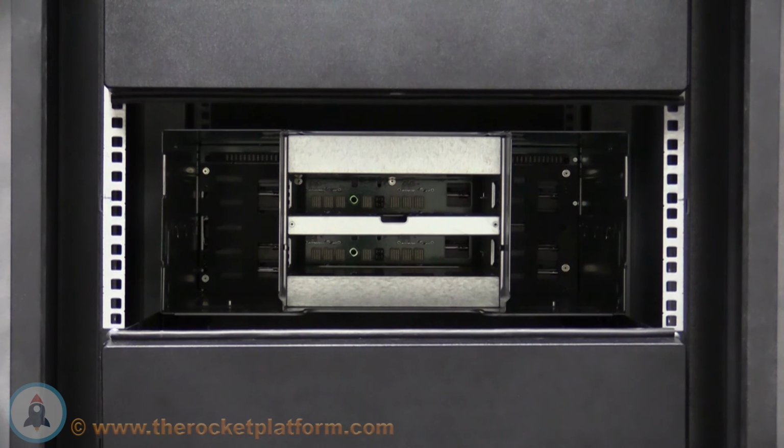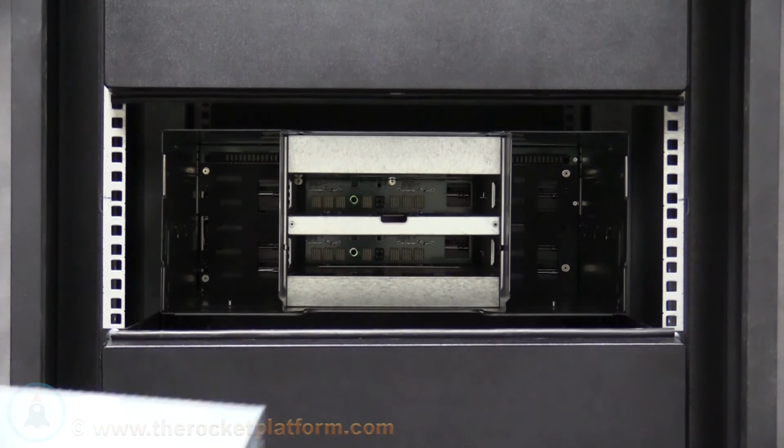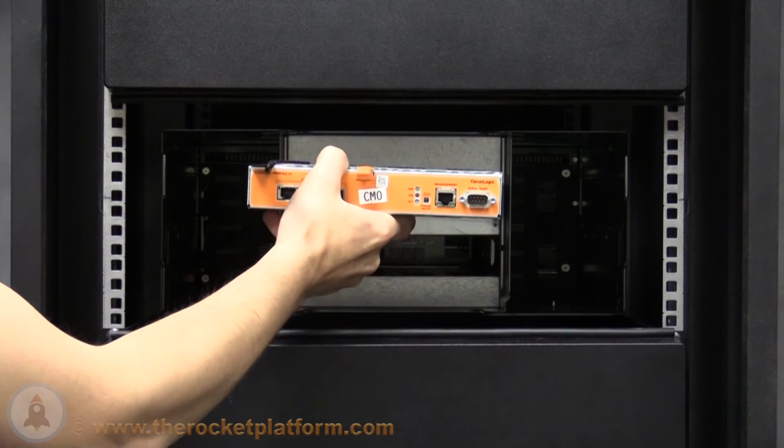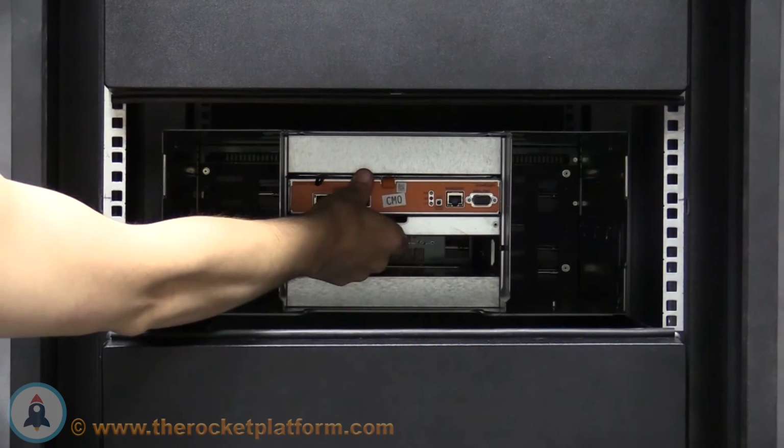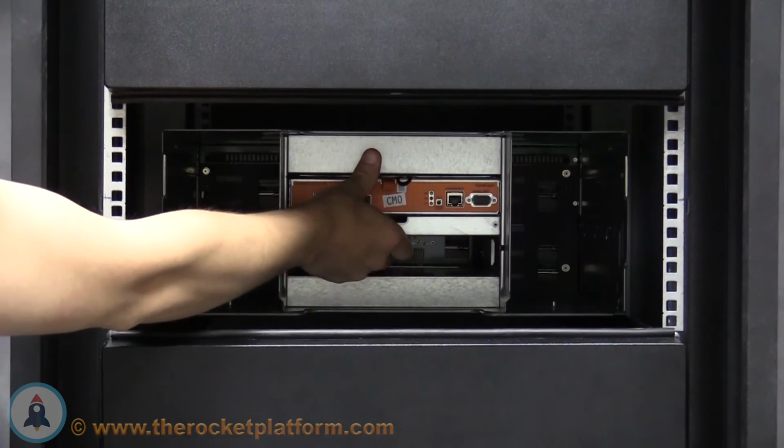You will now have to insert the rear components into the replacement chassis. Start with the control modules. To insert the control module into the slot, open the lever on the controller all the way. Insert the controller into its correlating slot, ensuring that the orange tab is on the top of the controller and the connector pins are facing in toward the center of the chassis. Push back until the lever begins to catch. Once the lever has begun to catch, push back on the lever until you see or hear the orange tab click into place.